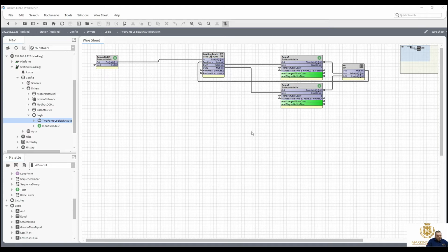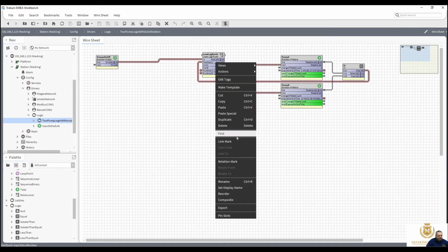You've got DPs, differential pressure switches, as an input. If it's inverter driven, you may have an inverter pump 1 fault, inverter pump 2 fault. You may have run statuses from the inverter. There's different ways. So we're going to try and expand on this basic pump logic to incorporate other future requests by clients, let's say. So first of all, let's get rid of this lead lag runtime, this default block.